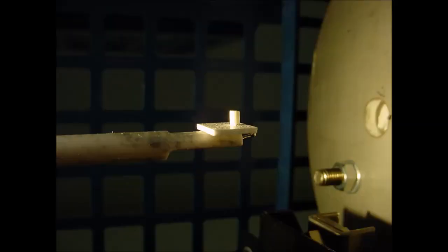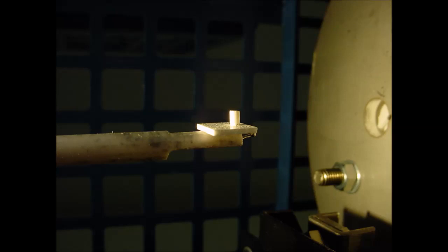In order to carry out the softening and melting tests, the Hot Stage Microscope MISURA HSM uses a cylindrical specimen with 2 mm of diameter and 3 mm of height. This specimen is prepared with a small manual press which is supplied with the instrument. It is also possible to follow the behavior of specimen with an irregular shape or analyze 2 specimen at a time.